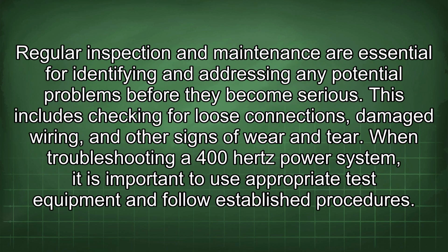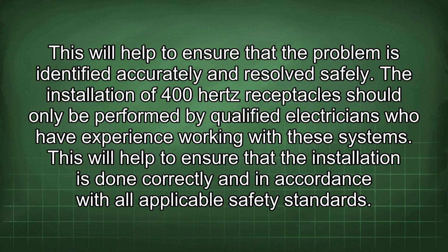Regular inspection and maintenance are essential for identifying and addressing any potential problems before they become serious. This includes checking for loose connections, damaged wiring, and other signs of wear and tear. When troubleshooting a 400 Hz power system, it is important to use appropriate test equipment and follow established procedures. This will help to ensure that the problem is identified accurately and resolved safely. The installation of 400 Hz receptacles should only be performed by qualified electricians who have experience working with these systems. This will help to ensure that the installation is done correctly and in accordance with all applicable safety standards.